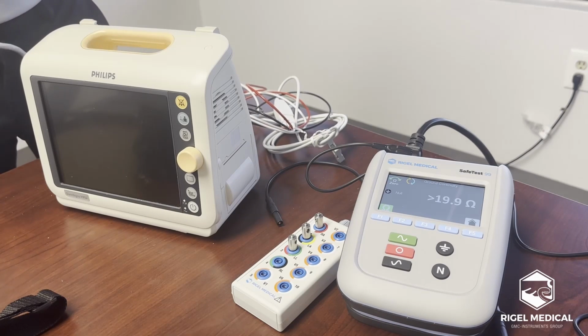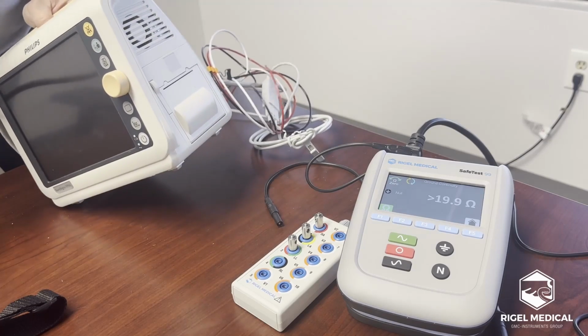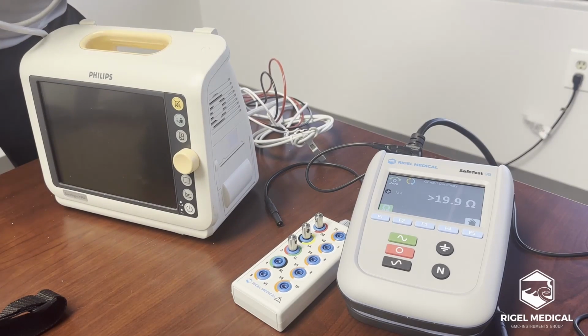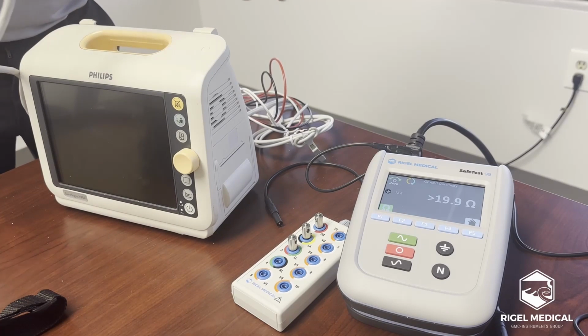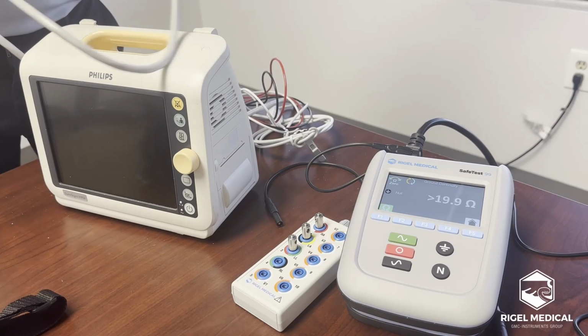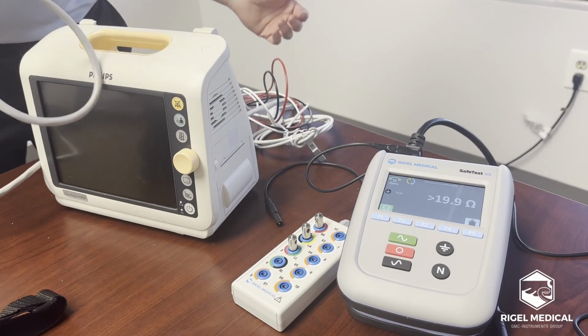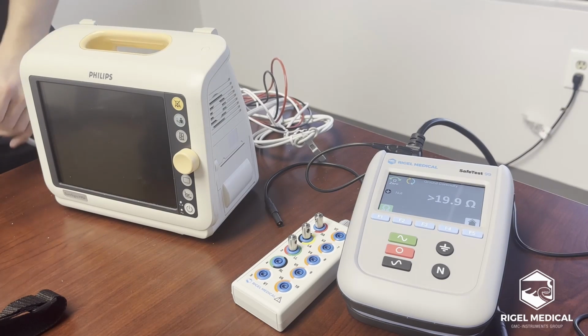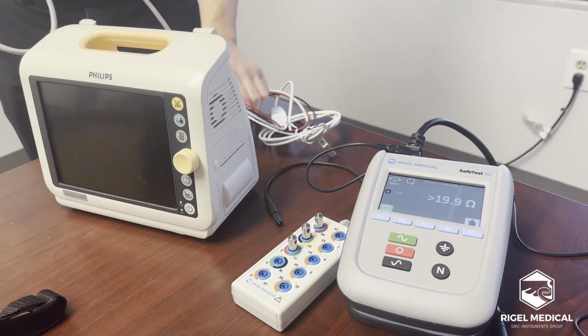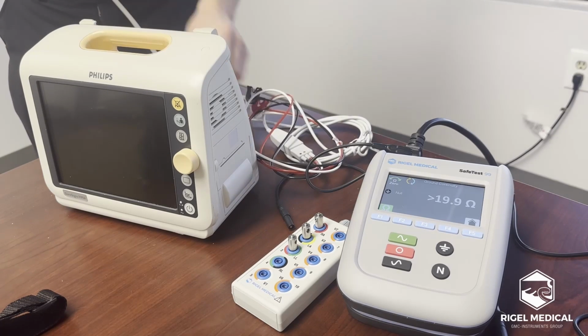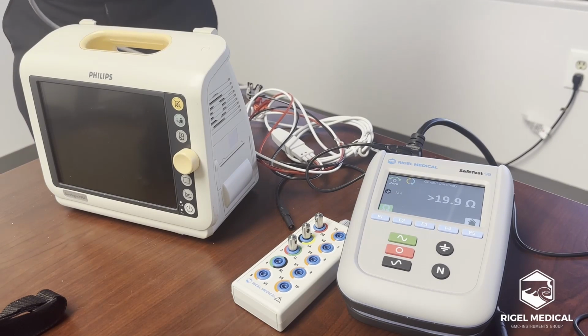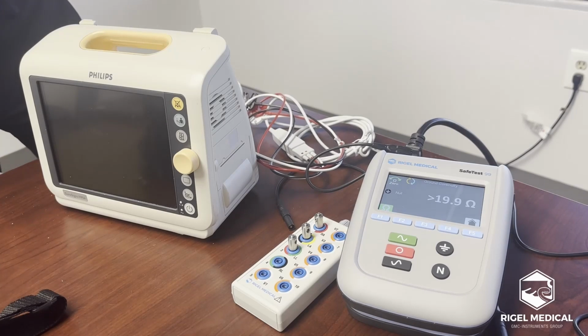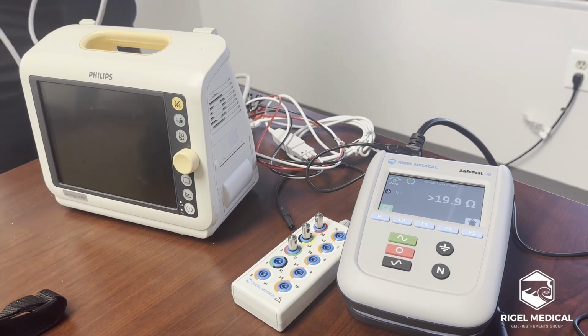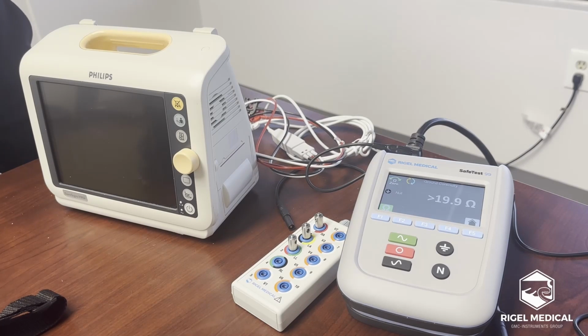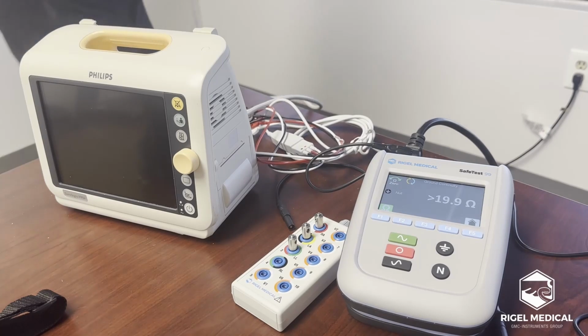So we're looking at a couple of things. Does the device have any cracks? Is it damaged? Is it in general good condition? So it's all common sense things to look out for. We also look at the cords to see if there's any frayed wires, if the plug's damaged, does it have the correct amperage rating. And we can also test the stress relief, because that's part of the NFPA 99 schedule. You need to look at the stress relief of the cord. Does it still have good integrity once it's been put under that strain? So one way to do that is just during the ground continuity test, which is the first test when performing electrical safety.